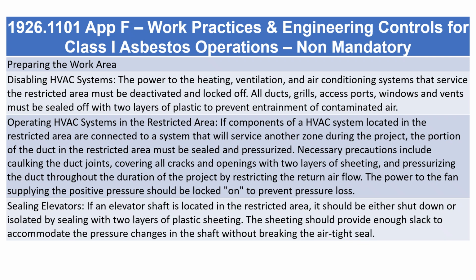If components of a HVAC system located in the restricted area are connected to a system that will service another zone during the project, the portion of the duct in the restricted area must be sealed and pressurized. Necessary precautions include caulking the duct joints, covering all cracks and openings with 2 layers of sheeting, and pressurizing the duct throughout the duration of the project by restricting the return airflow. The power to the fan supplying the positive pressure should be locked on to prevent pressure loss.